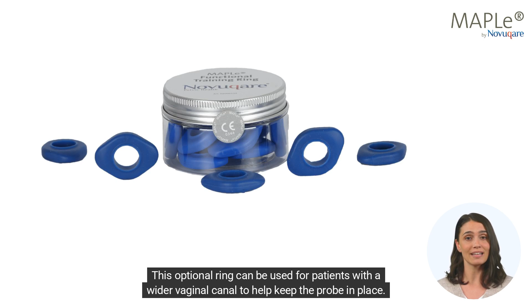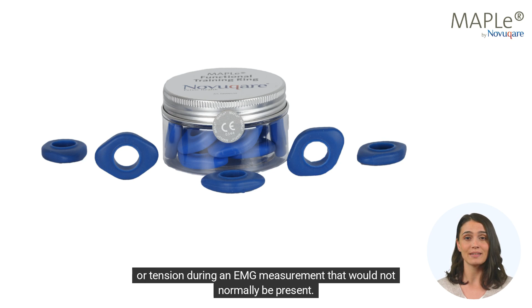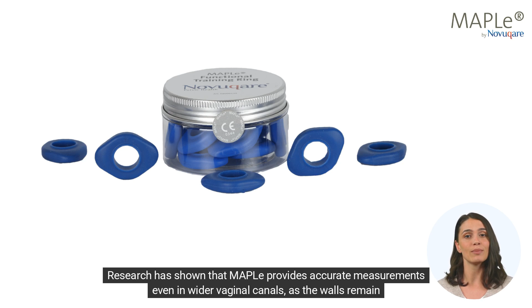Functional training ring. This optional ring can be used for patients with a wider vaginal canal to help keep the probe in place. Be aware that this ring is officially intended for training purposes only, as it may create pressure or tension during an EMG measurement that would not normally be present. Always record the use of this ring in the app, and do not compare the results with the reference scale. Research has shown that MAPLe provides accurate measurements even in wider vaginal canals, as the wall remains in contact when at rest.